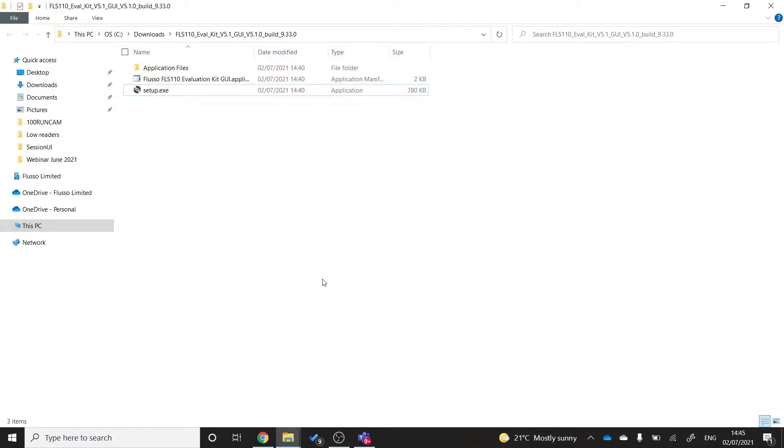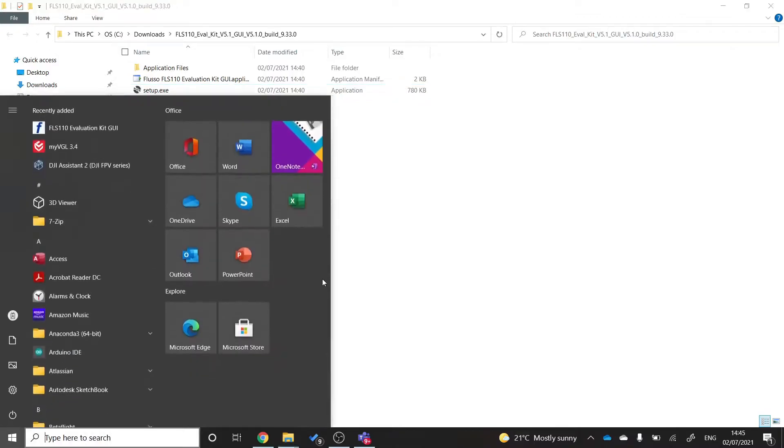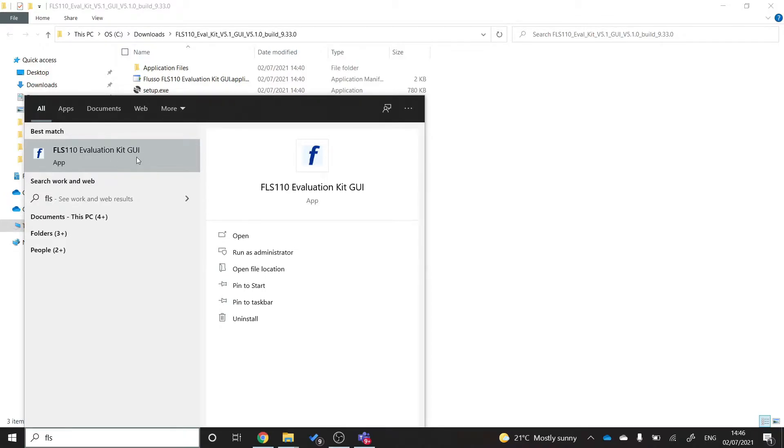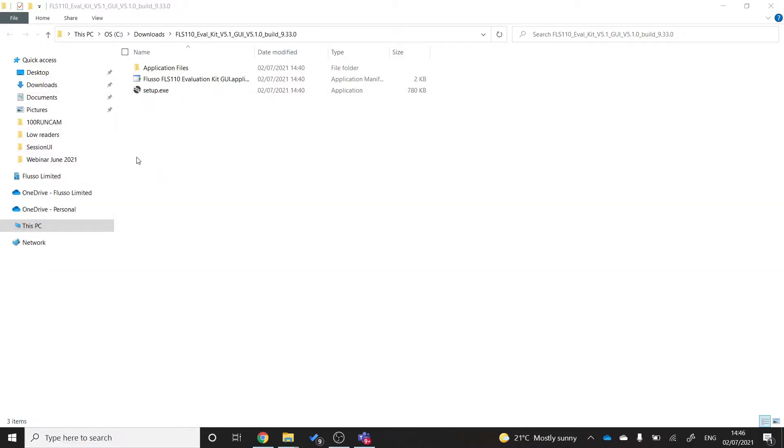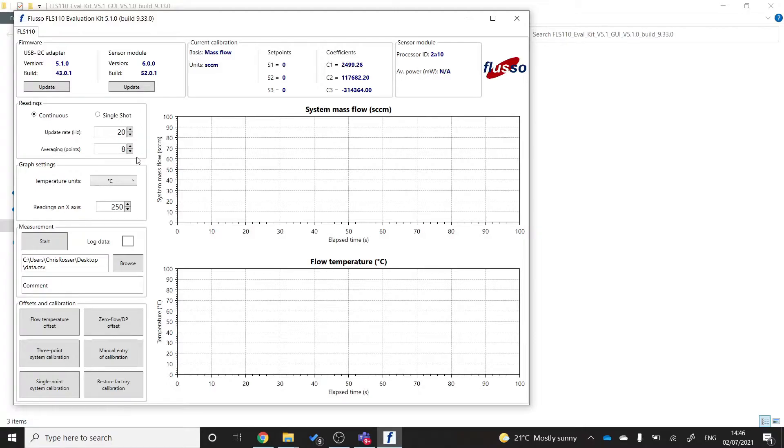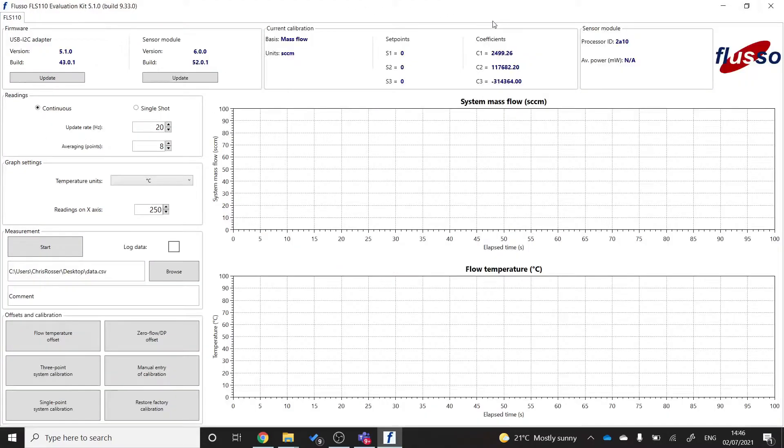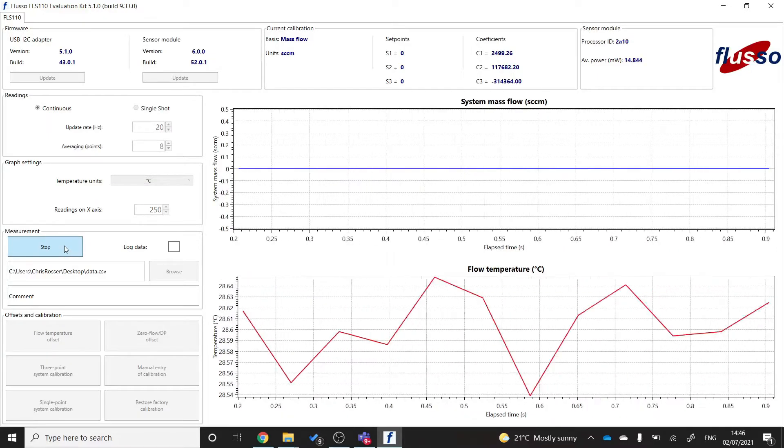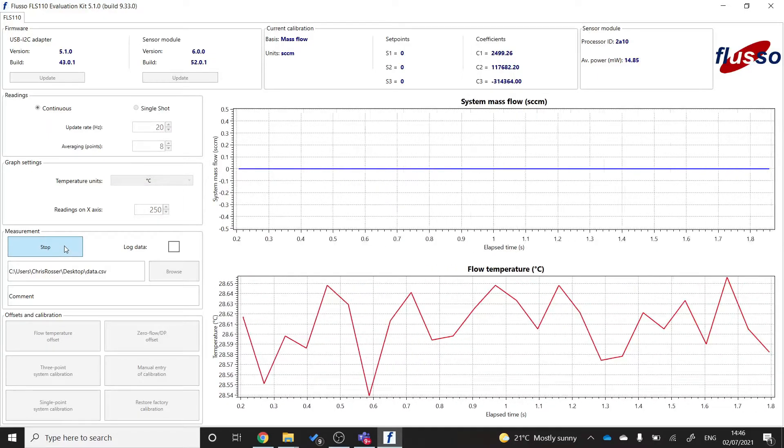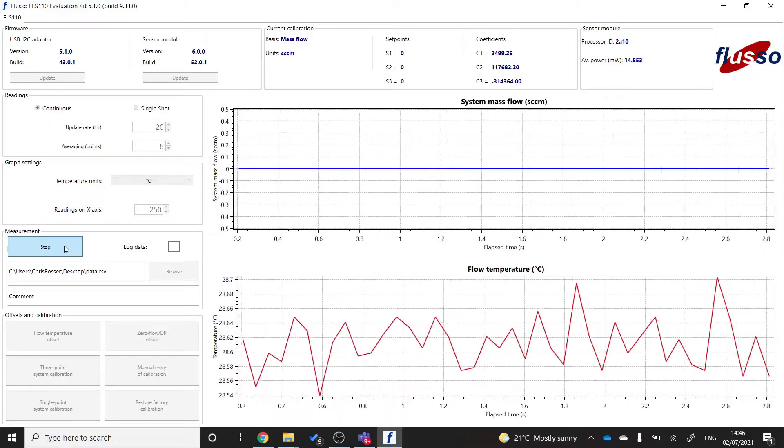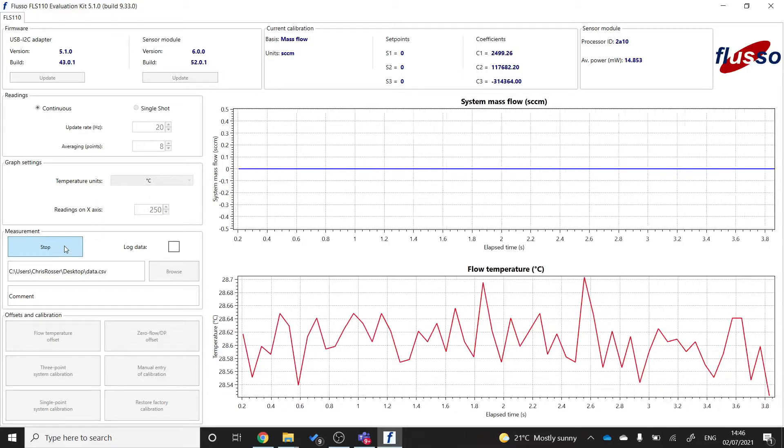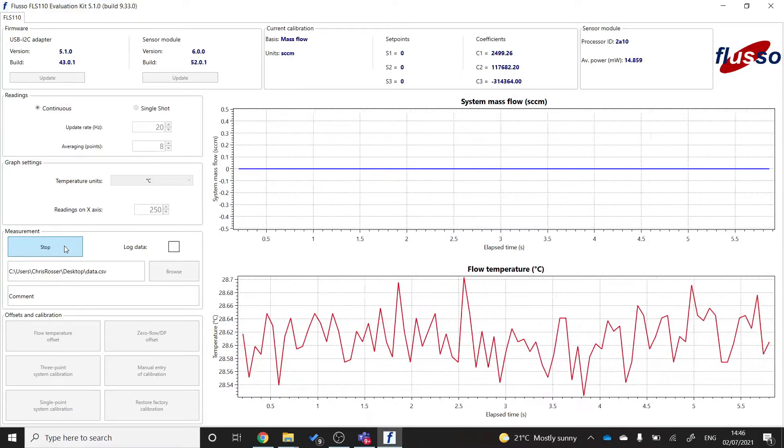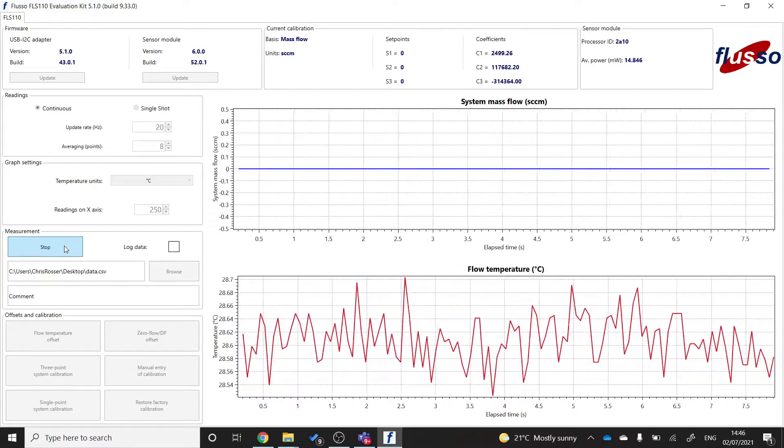Once everything is connected and ready to go, you simply search for FLS on your start menu and you should see this evaluation kit GUI application come up. If you run that, you should see this screen. This is the FLS110 evaluation kit GUI. And the first thing you'll want to do is just check that the sensor is working. So let's go ahead and start the sensor. It's this button here. And we can see that initially the sensor is reporting zero flow and a temperature of 28 degrees.